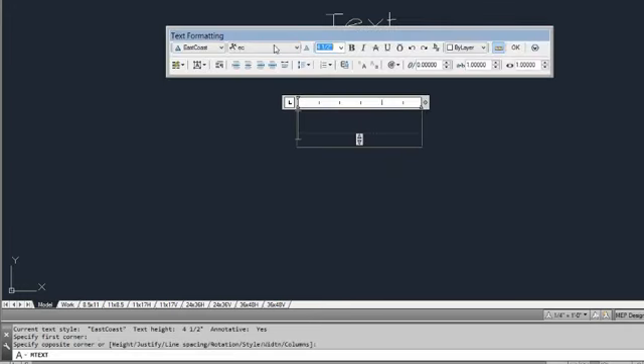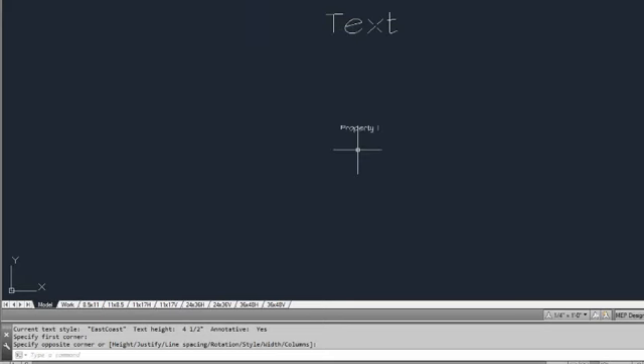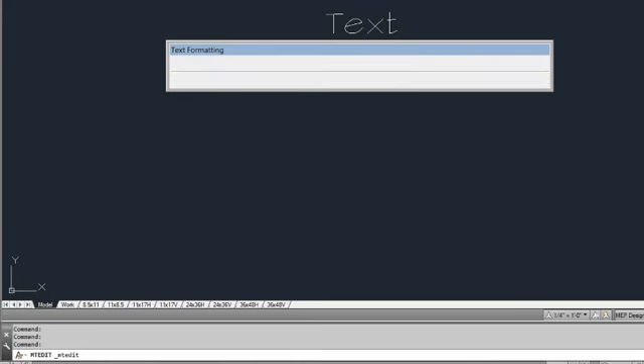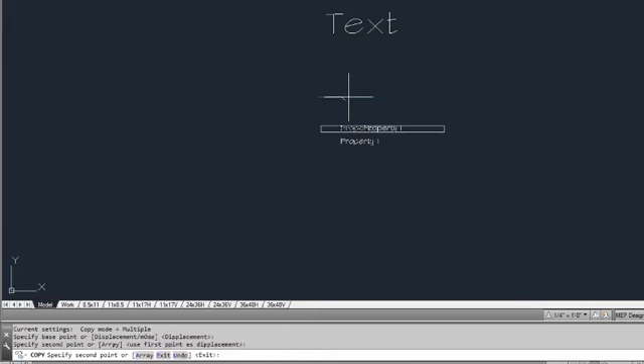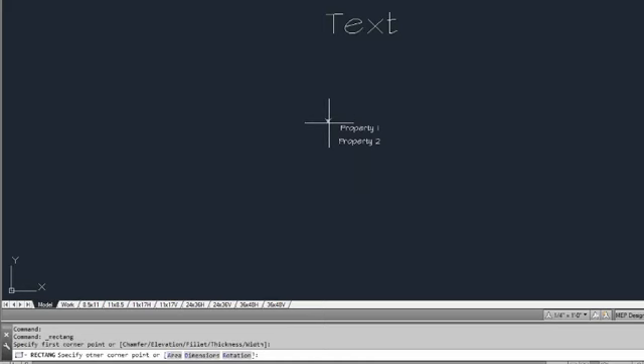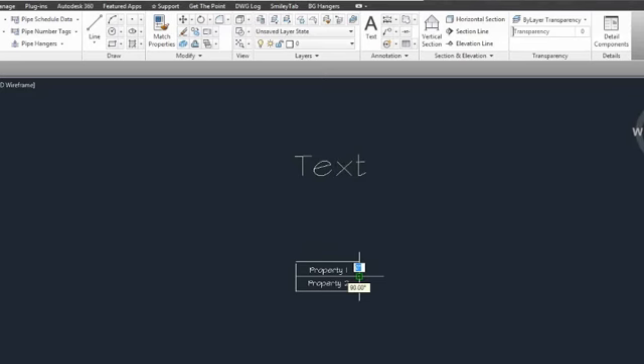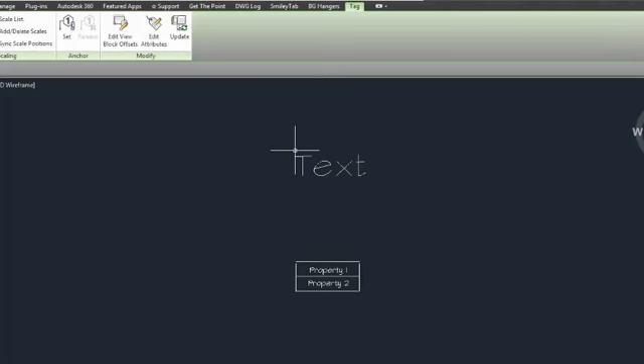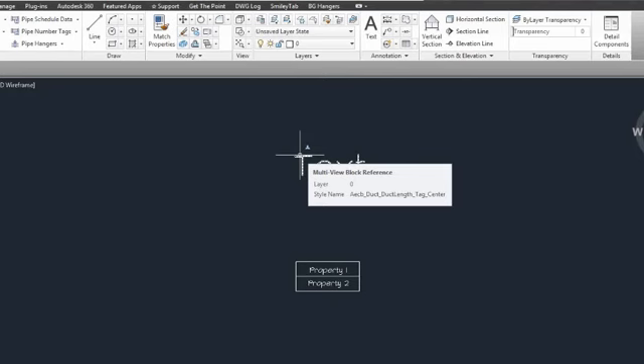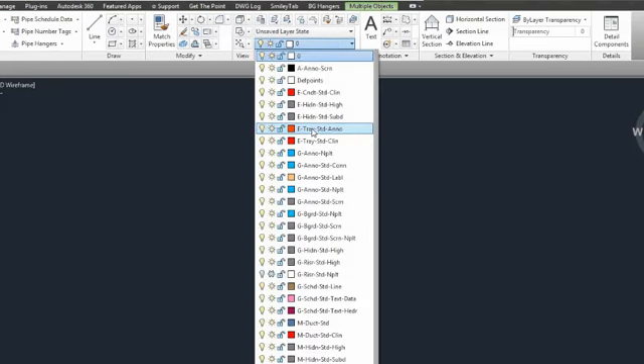Let me go back and create another tag — a multi-property one. I'll make text one inch tall, middle center, and call it 'property one,' then copy it down and call it 'property two.' Having distinct names is important so you can tell them apart later. I'll also put a box around these graphics. Note that I'm doing everything on layer zero, so tags work just like blocks — layer zero means the tag takes on whatever layer properties the tag is placed on. You can hard-code a layer to force the tag there every time.